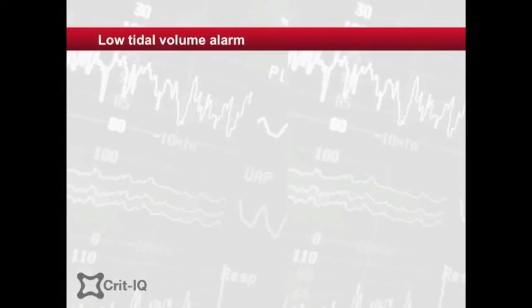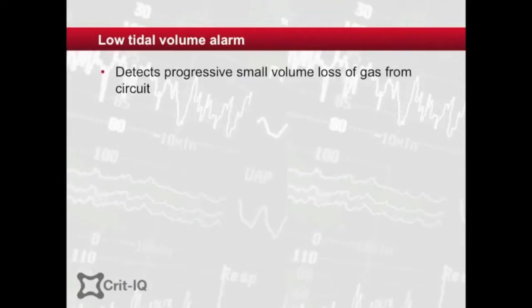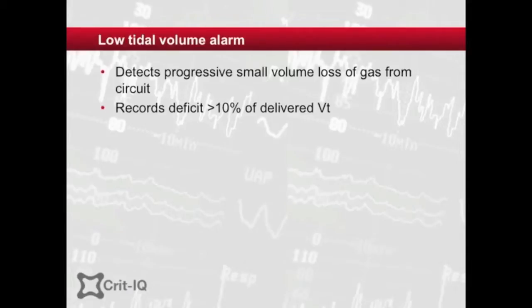Volume and minute volume alarms are designed to measure more subtle loss of gas from the ventilator circuit–patient system. Usually they are set to record a deficit in expiratory volume from inspiratory volume of greater than 10%. These alarms will be triggered by smaller leaks than pressure alarms. Examples include a leak around an under-inflated cuff, through an access port in the system, and from suctioning.